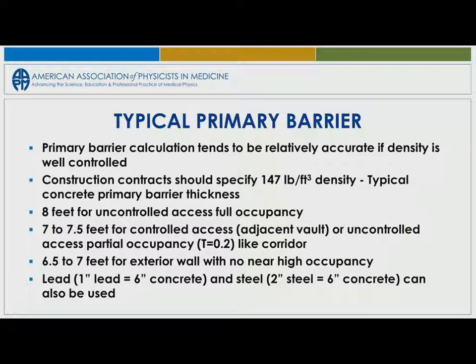Your primary barrier calculation tends to be - at least from lessons learned from my surveys, I don't think you find it written anywhere - typically relatively accurate if your density is well controlled. If you know you have the right density of concrete, your survey measurements will really match very well to what you calculated. What I recommend is put a fudge factor in there. Don't ever shield it to the minimum - put a fudge factor in there so you have a little safety factor.